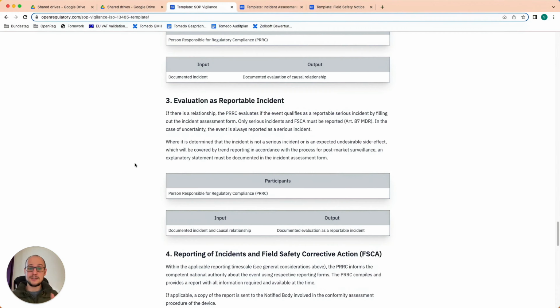But now you're faced with 10 occurrences and it's only mid-March. So in that case, depending on your risk management data and statistical extrapolation, you might be required to report such a significant trend change as well. That's what's mentioned here for full compliance. But this entire topic is more related to risk management and especially post-market surveillance. So for more context, it might be helpful for you to watch those videos again.